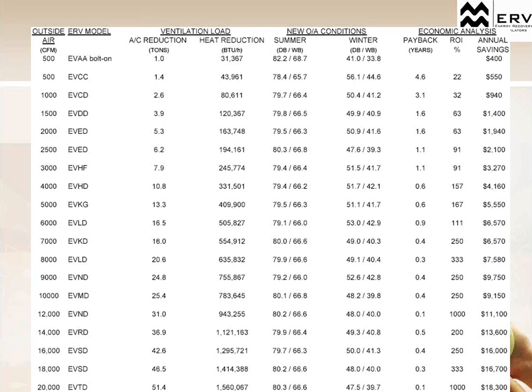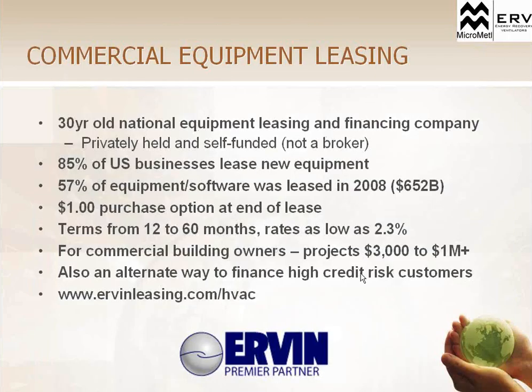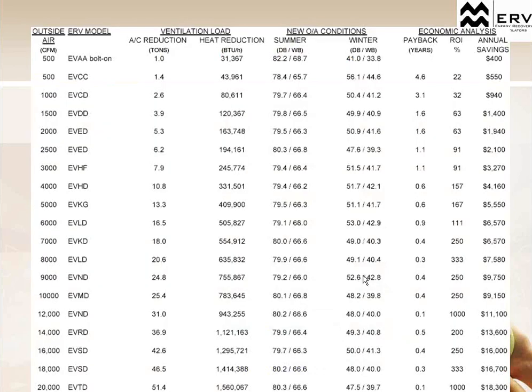So we've broken that down. We've got some of the values just to give you an idea of how remarkable the payback is on a simple ERV system. It's a very basic component that we can add to something as simple as a rooftop unit on a building that uses a lot of ventilation for the space load. And we can get some serious savings. So a lot of retrofit applications are perfect candidates for ERVs, and even your new construction applications.